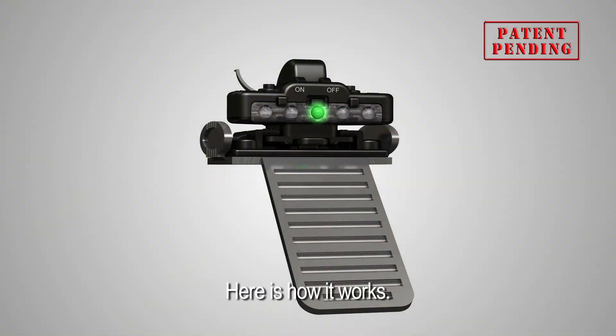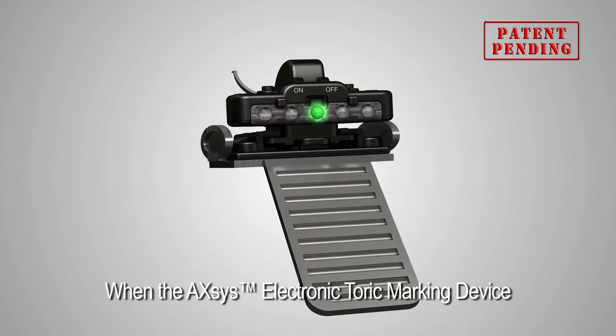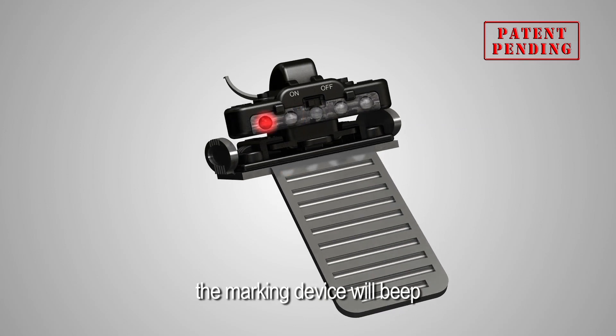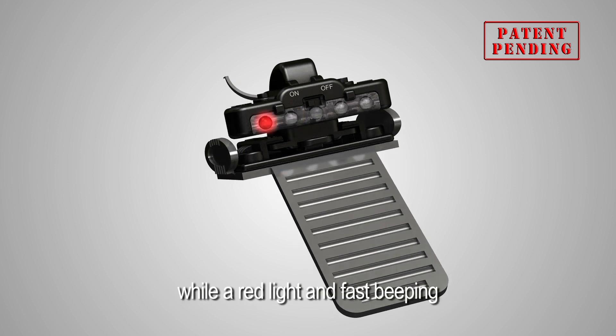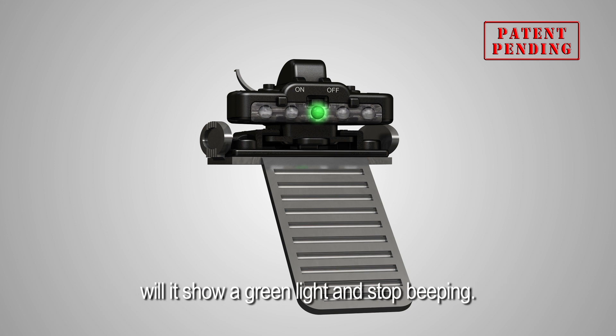Here's how it works. When the AXsys electronic toric marking device is tilted to the right or left, the marking device will beep and show an orange or red light. An orange light and moderate beeping indicates a slight tilt, while a red light and fast beeping indicates an extreme tilt. Only when the marking device is held perfectly horizontal will it show a green light and stop beeping.